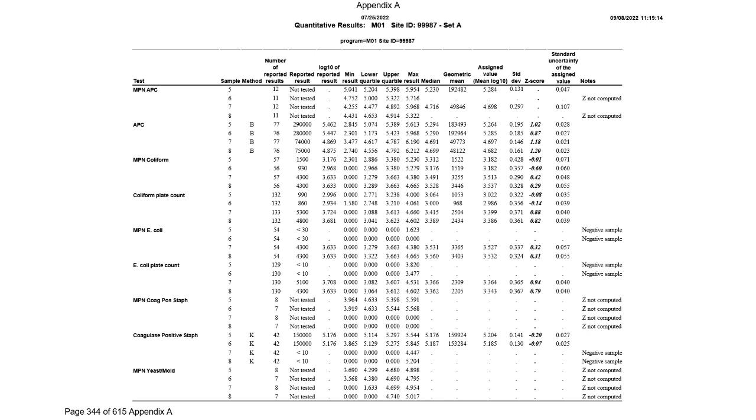We provide information on the quartiles, the median, then of course the assigned value, which for this program is based on consensus values because we have over 200 laboratories in this program, and the standard deviation, and the resulting z-score for that laboratory. Again, a z-score, anything under 2 is great.